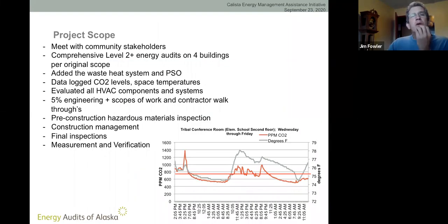So this is the project scope. Before I go into that - the graph in the lower right corner is one of the data logging graphs I created during the energy audit phase. The gray line shows the temperature on the second floor of the elementary school, and the orange line shows the carbon dioxide concentration. The red line just under 800 - it's supposed to be at 800, but it got shifted a bit - is the recommended highest level of CO2 in a building. One issue with these buildings was the ventilation wasn't working properly, so I wanted to see the air quality, and you can see it routinely exceeded the recommended 800 parts per million during the day.